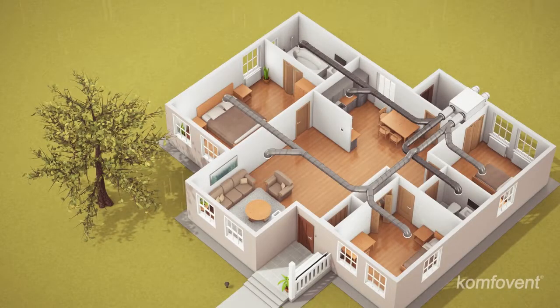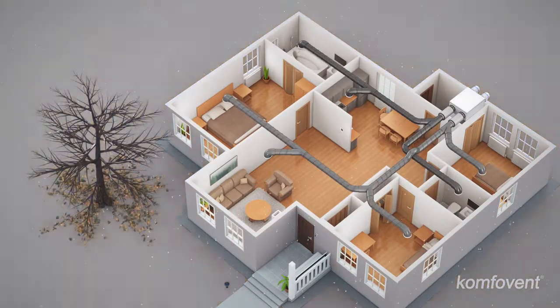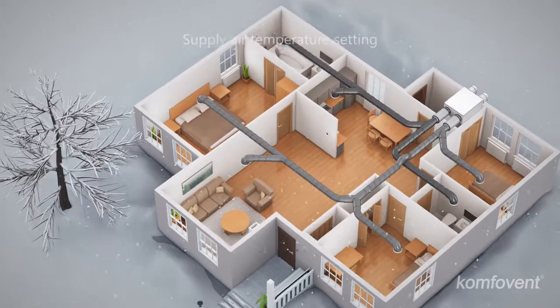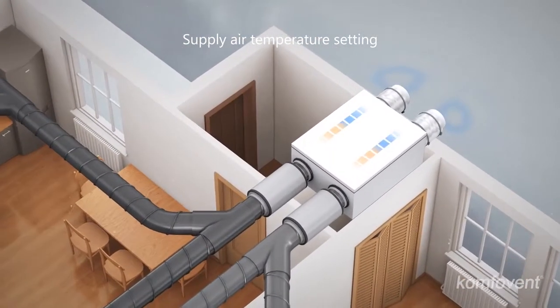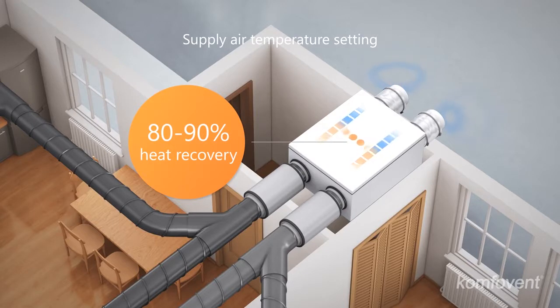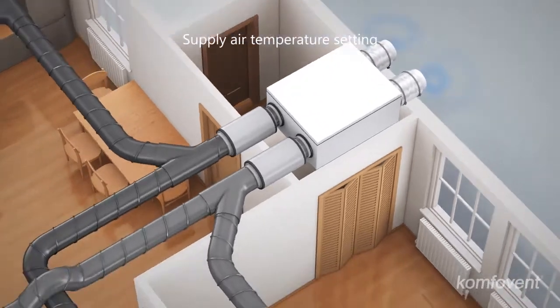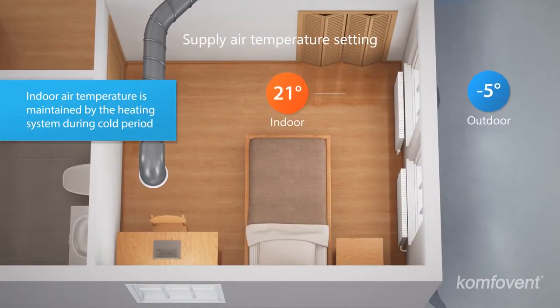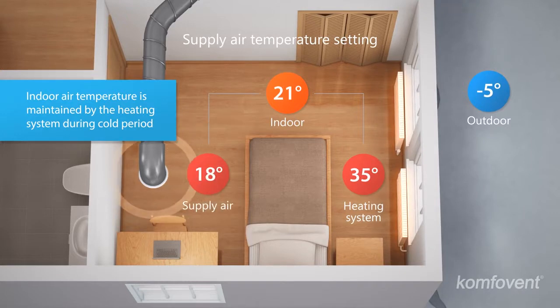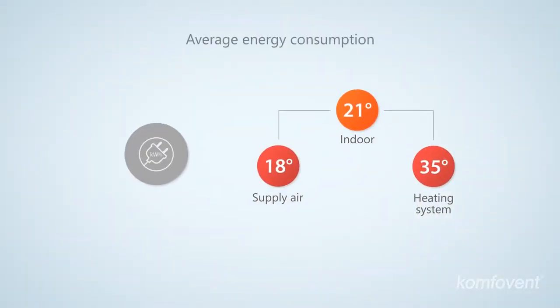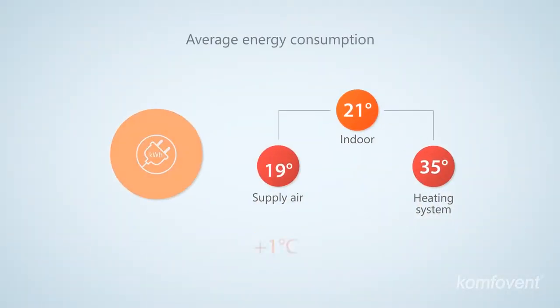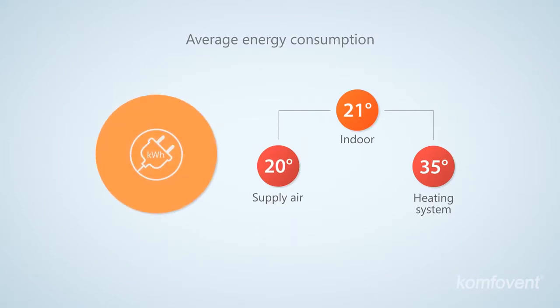The power consumption of the ventilation system directly depends on the air temperature settings. When choosing the air supply temperature, it is important to remember that the air handling unit recovers 80 to 90 percent of heat. A one-degree increase in the air supply temperature raises energy consumption on average by a quarter. Smart control allows you to manage the operation of the electric air heater.